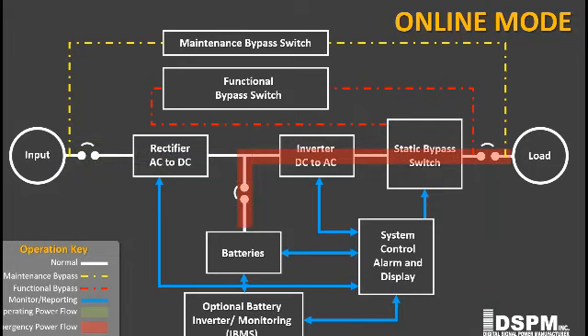Finally, in the event of a utility power failure, the red line shows the flow of power through the online inverter. Because this inverter is online 100% of the time, the status of the utility company's feed is invisible to your equipment or lighting since the batteries are in the power supply loop at all times. DSPM's maintenance bypass switch ensures the inverter is completely isolated from both power source and the load, guaranteeing technicians are safe when performing service or maintenance.